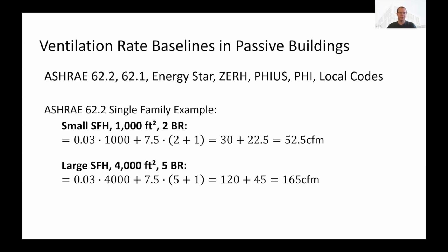But just a quick example, if we were to take a very simple single family home and dumb it down a little bit, we're going to get much smaller airflow rates, maybe 50 CFM minimum, 100 CFM, up to 100 or 200, maybe even more than that when we look at large single family homes. And this is a simple equation, but it's about the floor area and the number of bedrooms to give us the CFM rate. And I just want to point that out because there are a lot of engineers that are going to be doing different calculations and sizing based on these various standards.